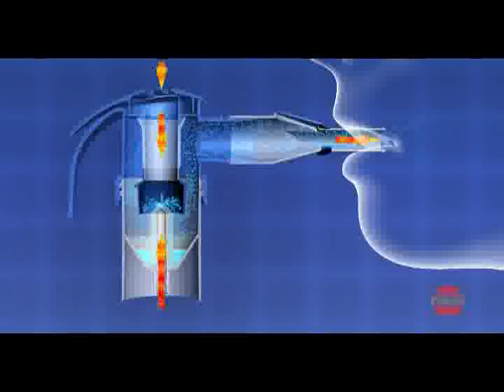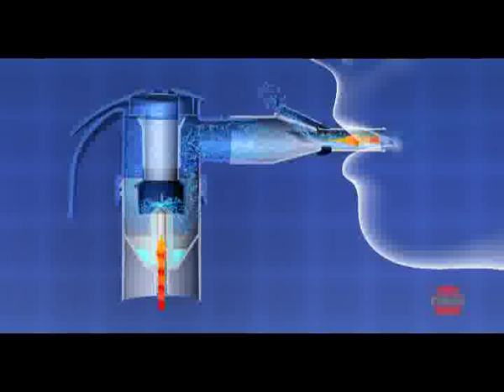Taking deep, slow breaths ensures optimum transport of the aerosol to the lung. The inspiratory valve then closes again on exhalation. The expiratory valve opens simultaneously, so this is the only way for the aerosol to escape. This valve system used in the nebulizers of the PARI LC Sprint family ensures economical usage of the medication.